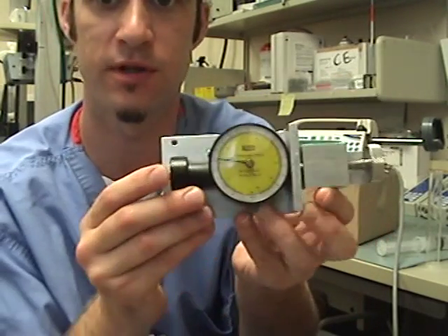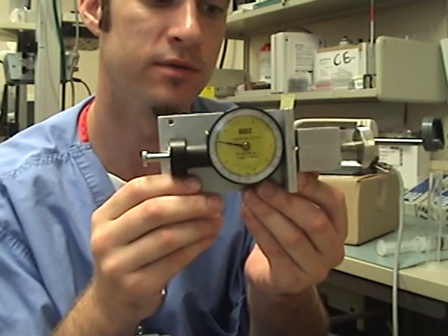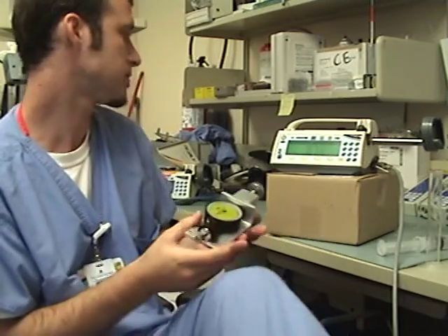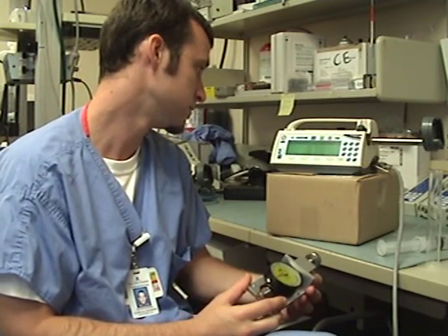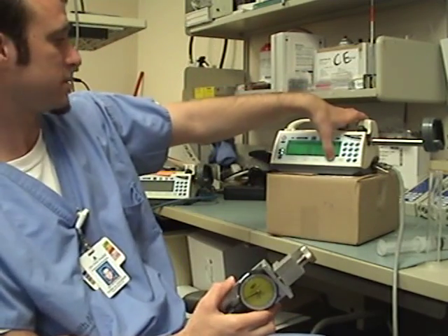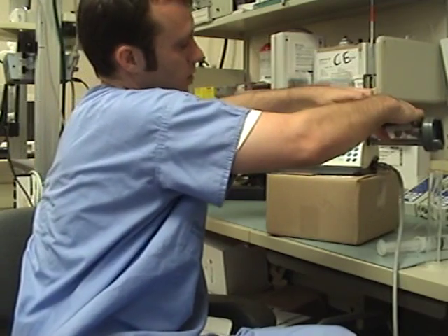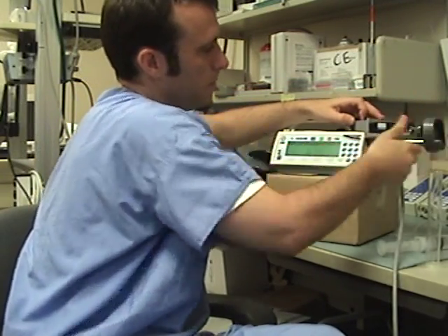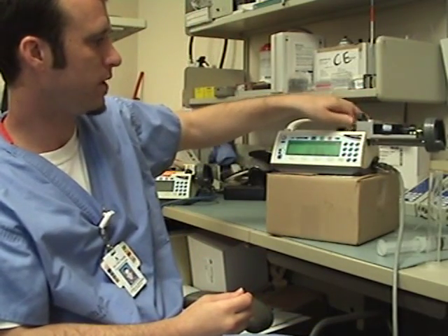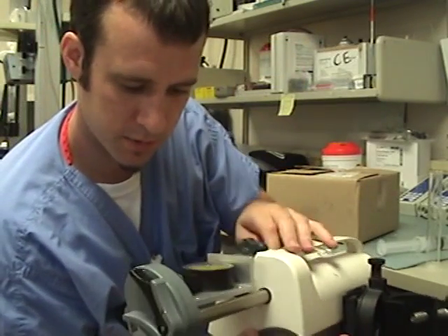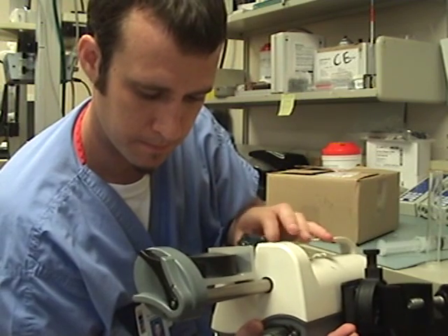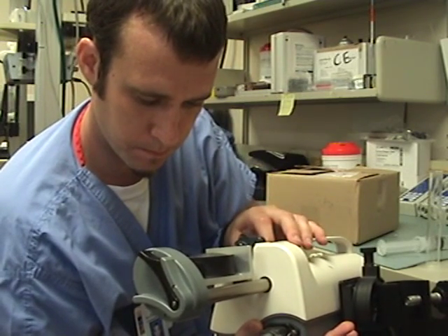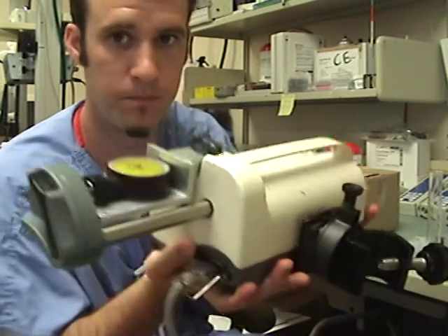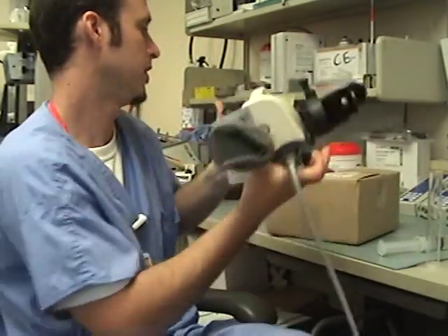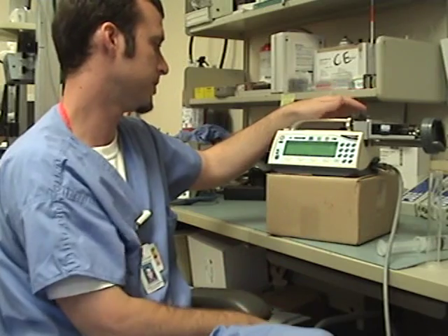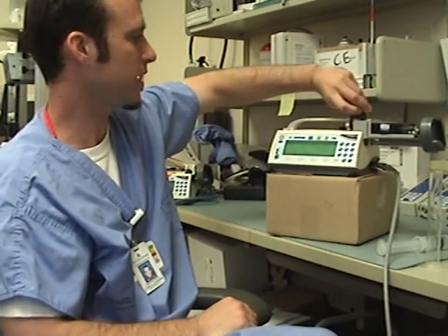This is the calibration pressure meter that we use for this device, also from the manufacturer. Now that the low standard is set and zeroed, we place our meter inside the device and crank it up to 10 pounds. There you go. And hit continue. Now the unit is set, force sensor is calibrated.